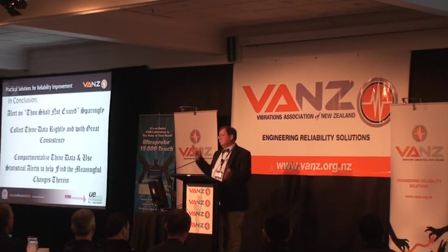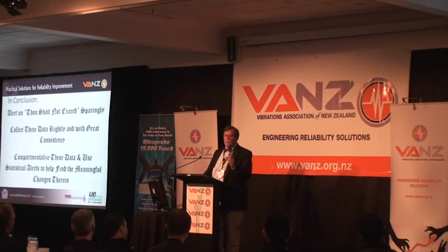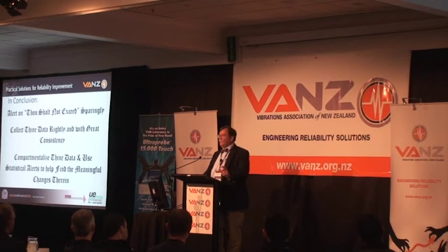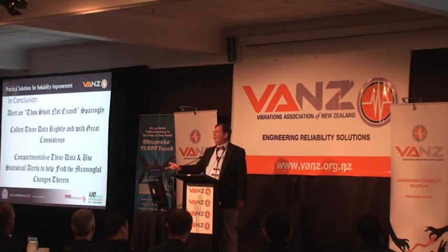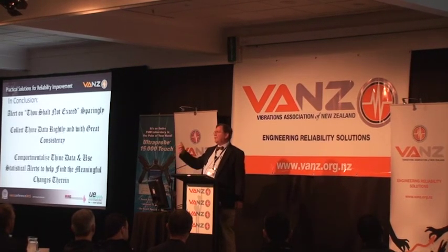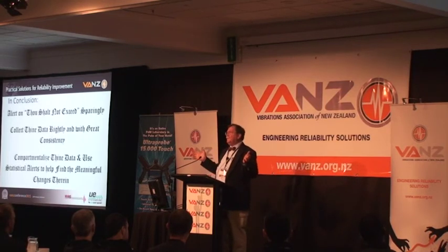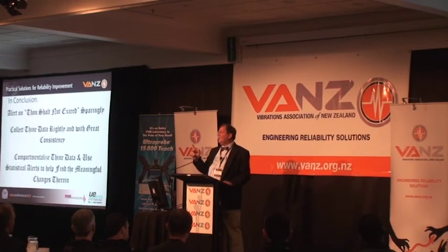A couple days later, we had this problem. When we were doing the investigation, after they changed it over, asking what's going on, what's the problem, they drew another sample of oil, sent it off to the lab, and it came back. When we got that report, they said to Pete, who was the tribologist on site, how could you miss this? This is horrible. There's this particulate, that particulate, all sorts of stuff. And we're talking a time span of much less than a week. I'm going to pose this as a non-rhetorical question to you guys. What happened?